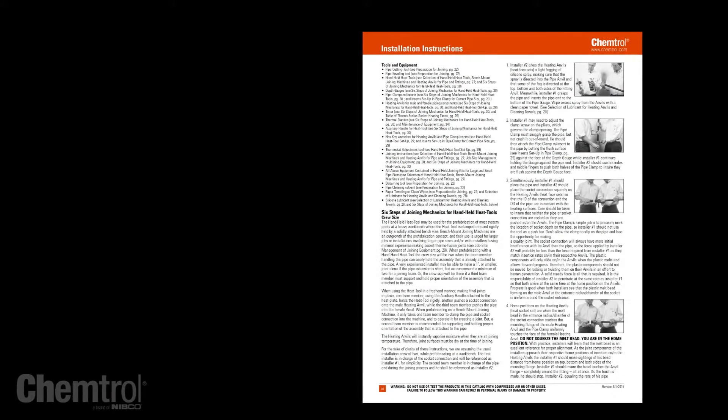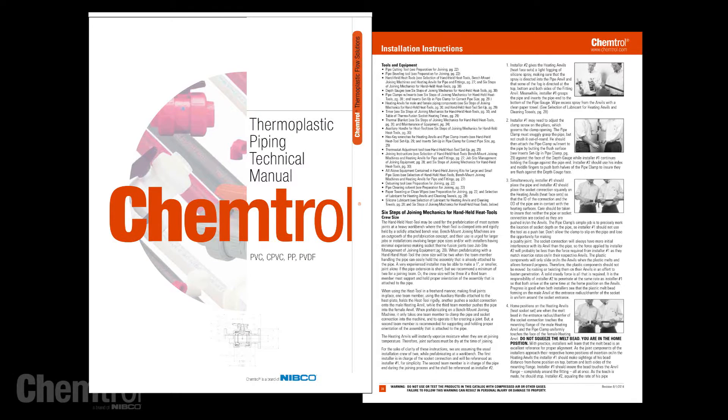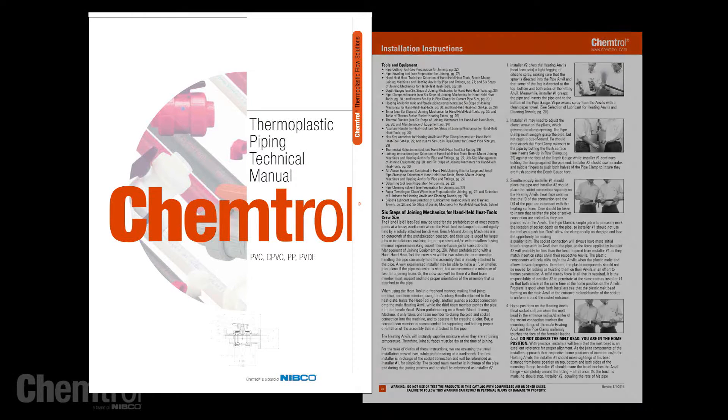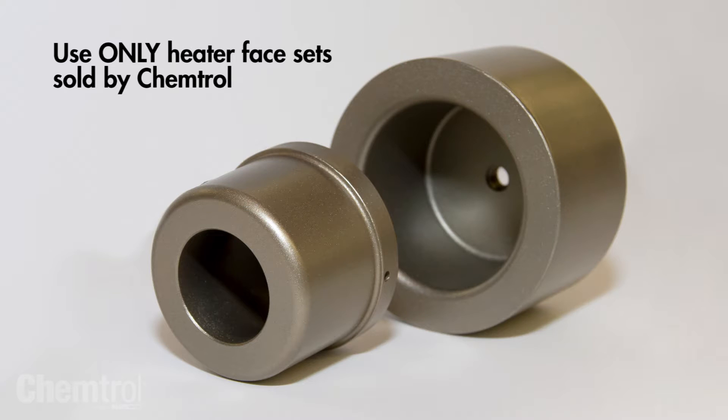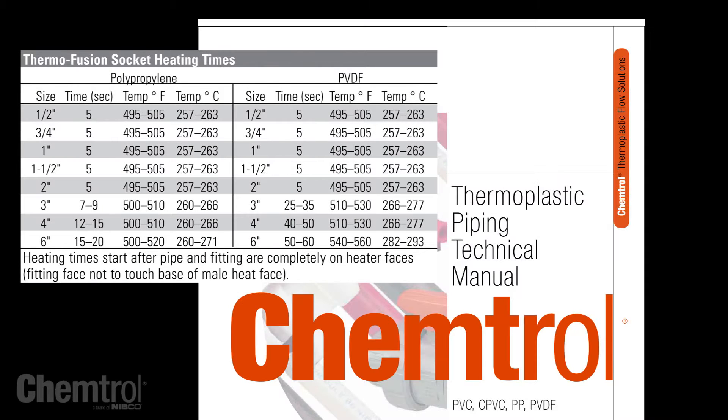Before beginning, view the installation instructions found in the Chemtrol thermoplastic piping technical manual. Only the heater face sets sold by Chemtrol are acceptable for use with Chemtrol pressure pipe and fittings. Follow the time and temperature chart published in the Chemtrol technical manual.